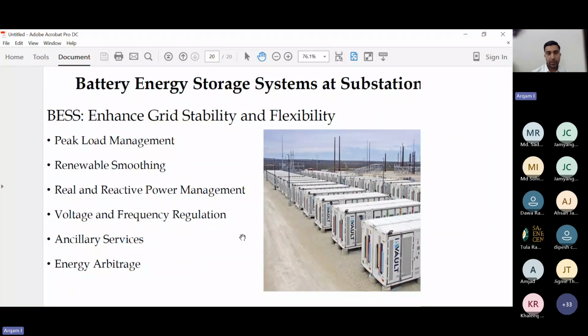And they also have the capability, because of the advanced control systems attached and the PCS systems built into the battery energy storage systems, to have very good control on real and reactive power management, whereby they can dynamically provide the reactive power needed to maintain voltage stability. Obviously, they can increase the voltage stability as well as the frequency stability, so the primary reserve as well as the requirements for all the variation in the power system.